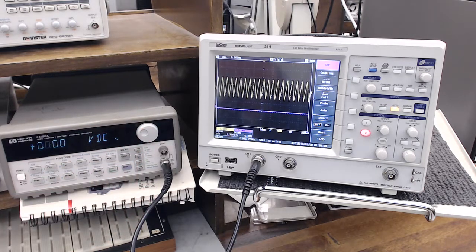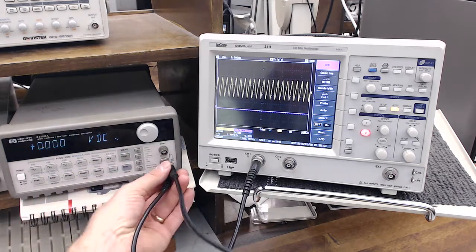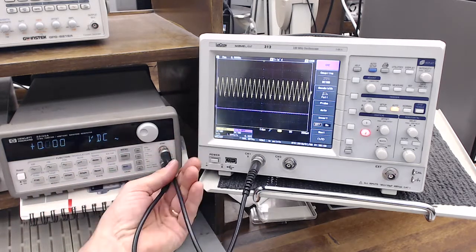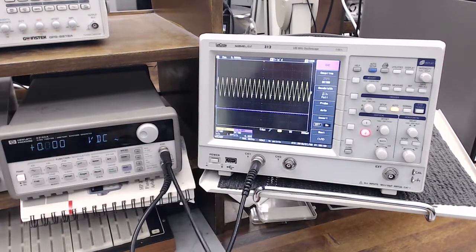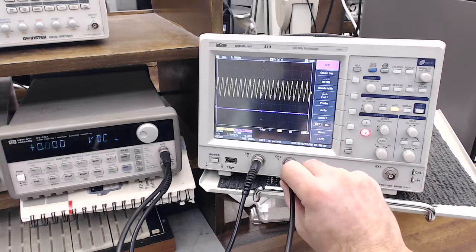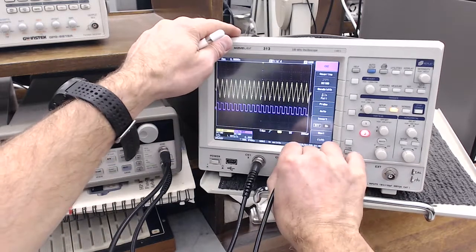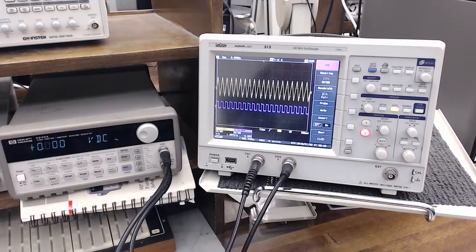And then think about the other output. The other output is called sync, or synchronize, and that is an output which is always the same waveform, always the same amplitude, but it's at the same frequency as the other one, and is at some phase relative to it. Okay, but at fixed phase.